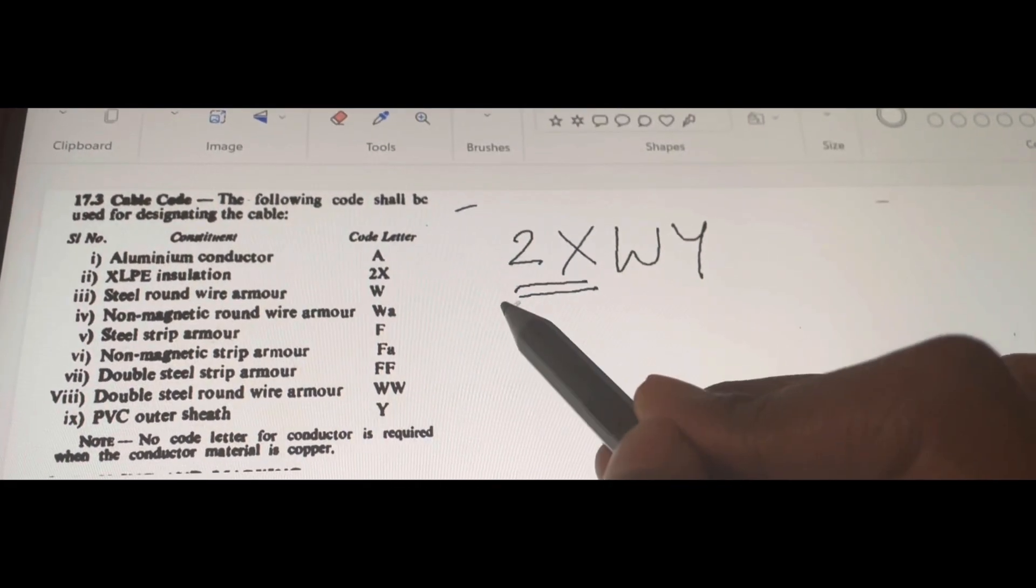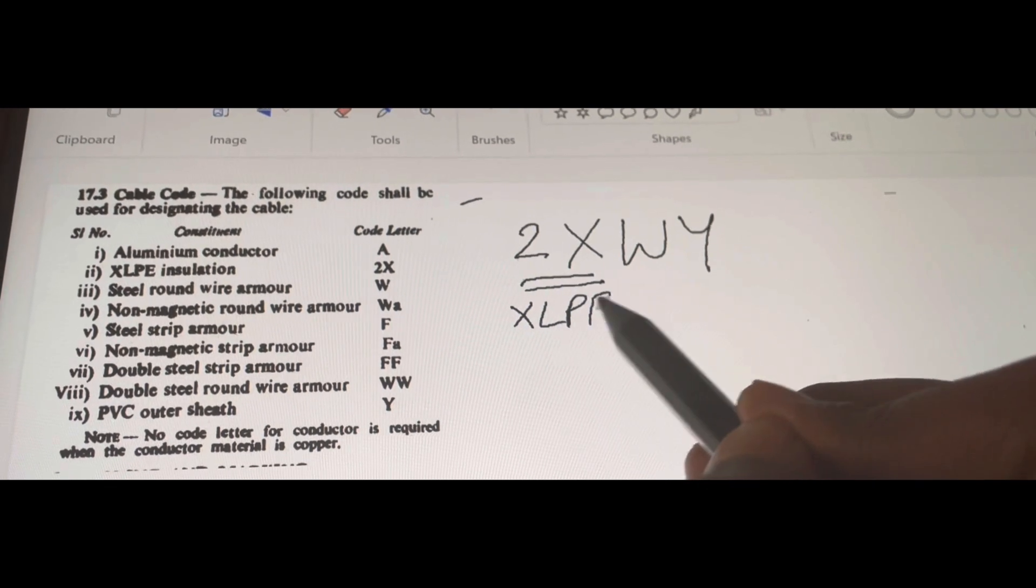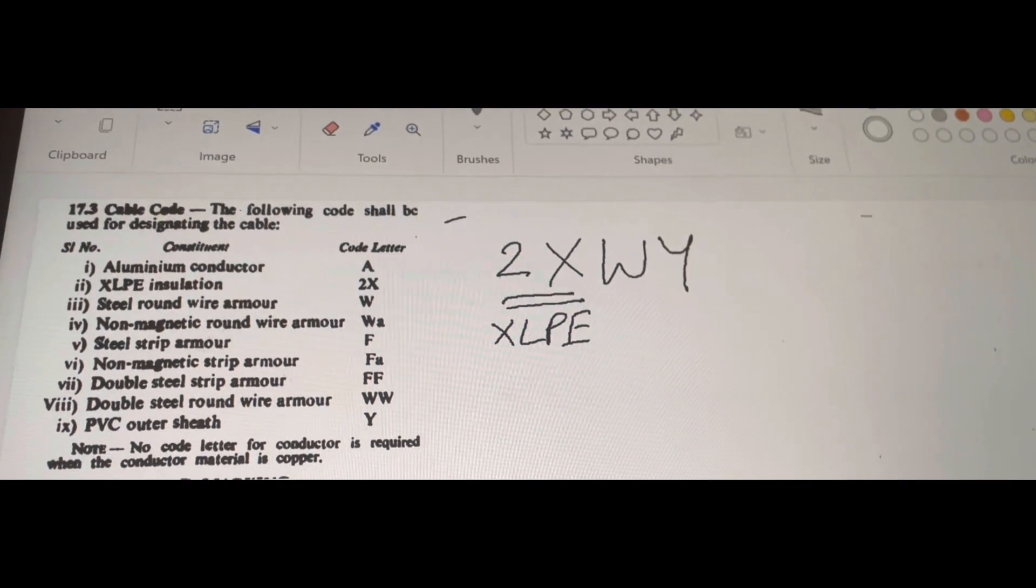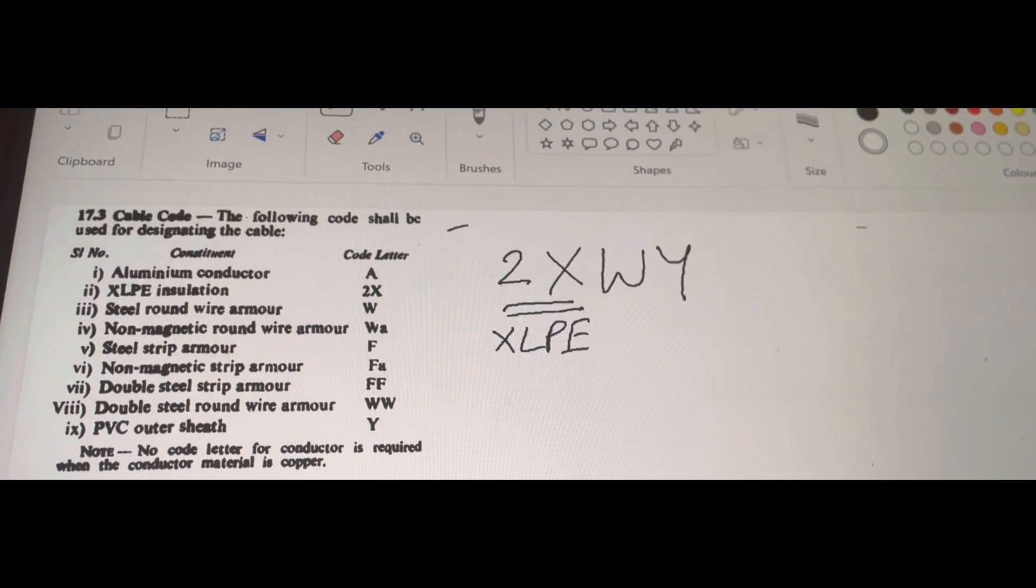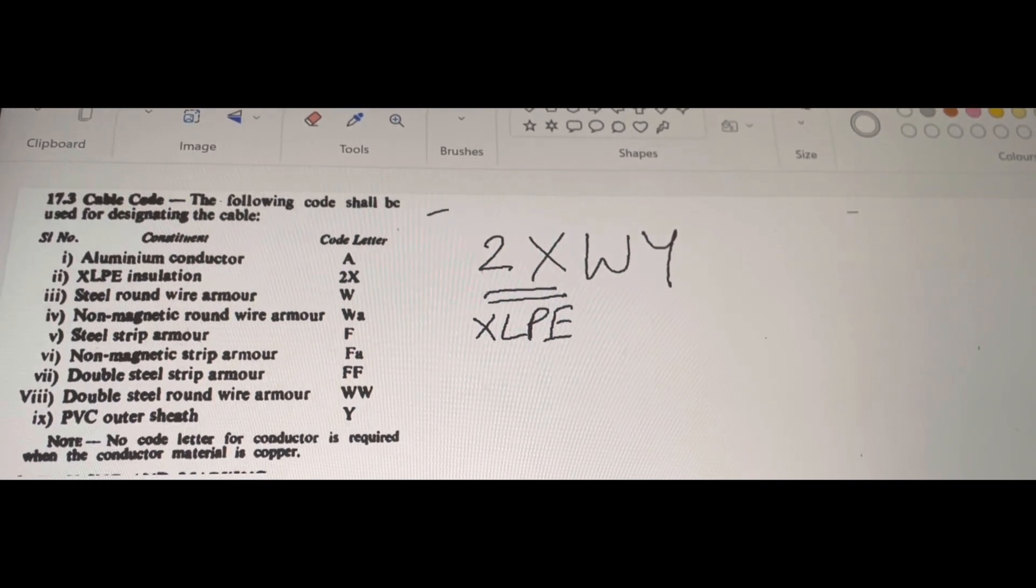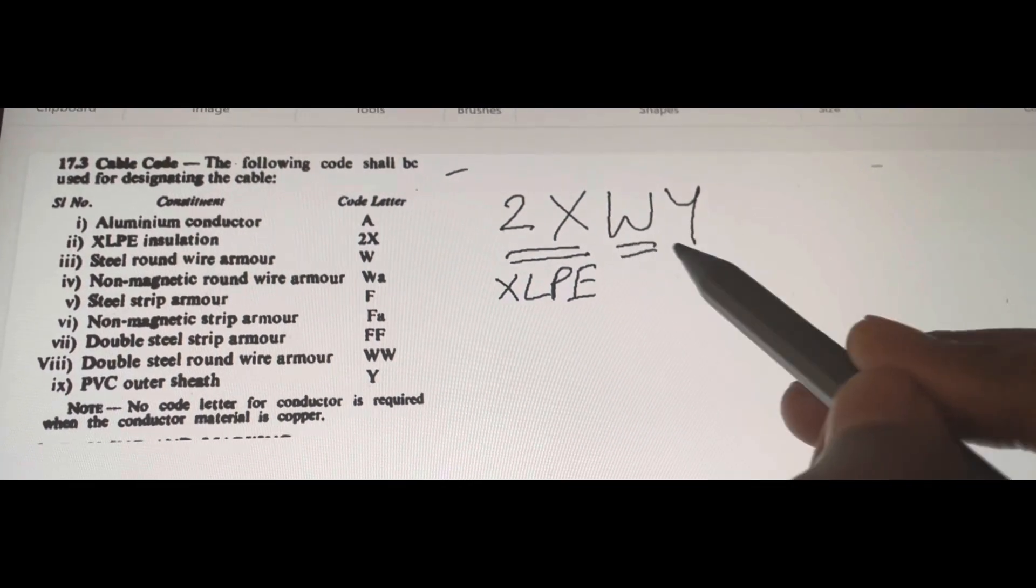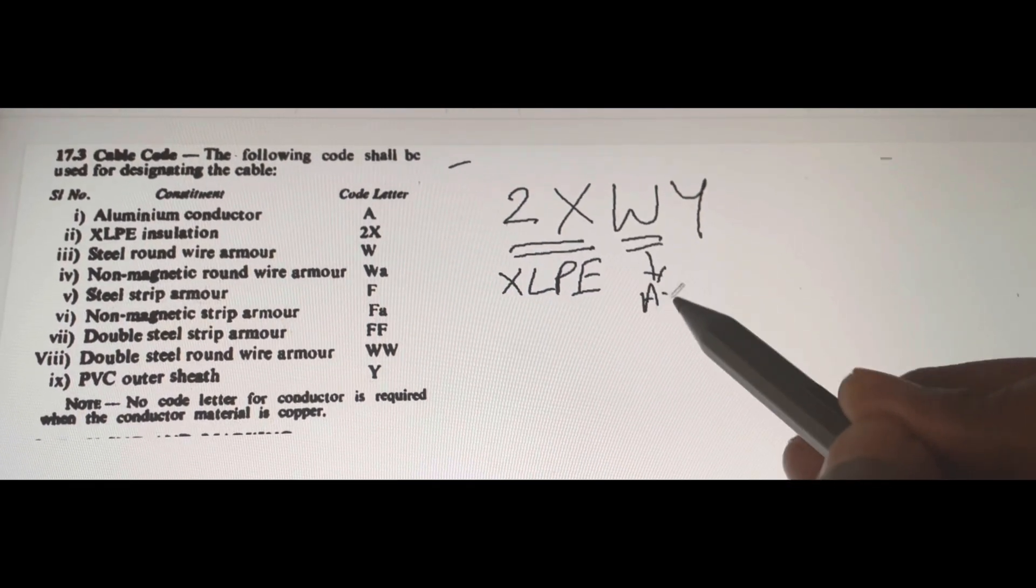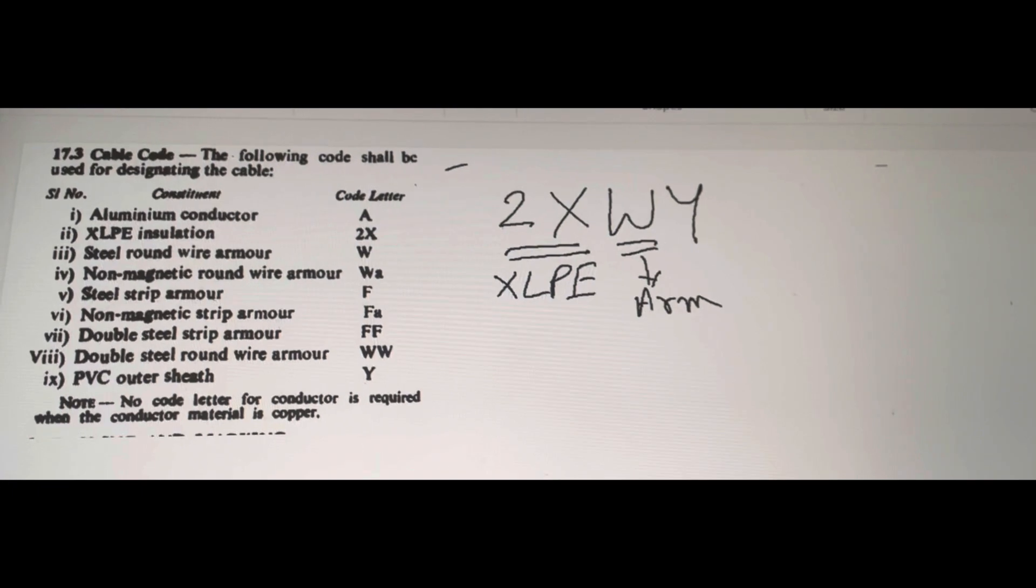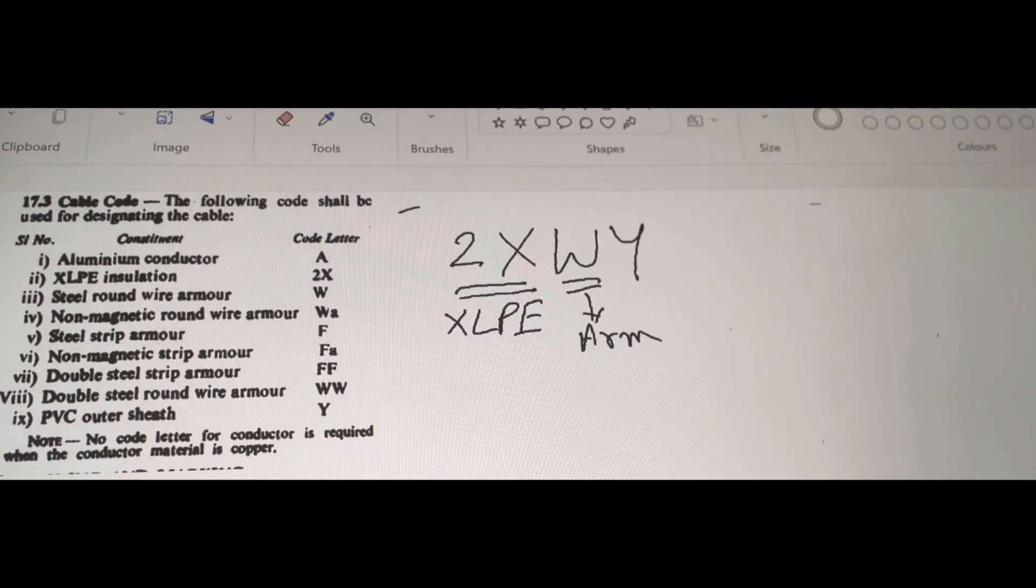The material is cross-linked polyethylene and the next letter w indicates that there is an armoring present in that particular cable and that is made up of steel armoring.